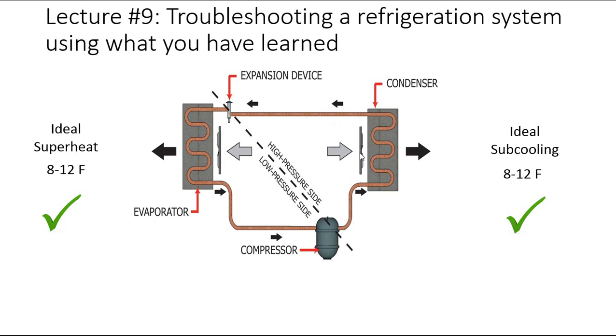Before you take your superheat and subcooling readings, it's really important to make sure that system has been running for at least 5 minutes before you actually take your readings. When the compressor starts and your fans start, it takes at least 4 to 5 minutes for this refrigeration system to become stable. I've seen a lot of technicians take their readings right when the compressor starts up, and they went the entirely wrong direction thinking they have a problem when they really don't.